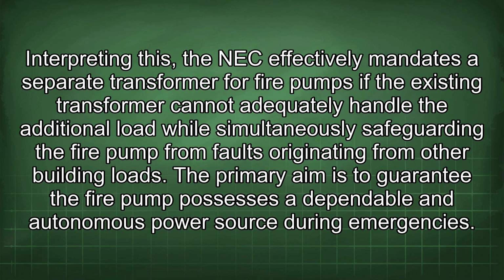Interpreting this, the NEC effectively mandates a separate transformer for fire pumps if the existing transformer cannot adequately handle the additional load while simultaneously safeguarding the fire pump from faults originating from other building loads. The primary aim is to guarantee the fire pump possesses a dependable and autonomous power source during emergencies.